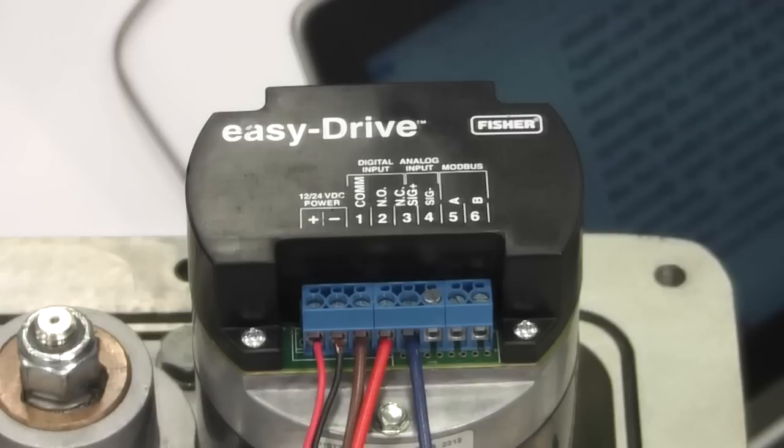If operating the valve in the L2E dual contact mode, the EZ-Drive should be wired at the common with the brown wire, normally open with the red wire, and normally closed with the blue wire. Terminals 1, 2, and 3 respectively.